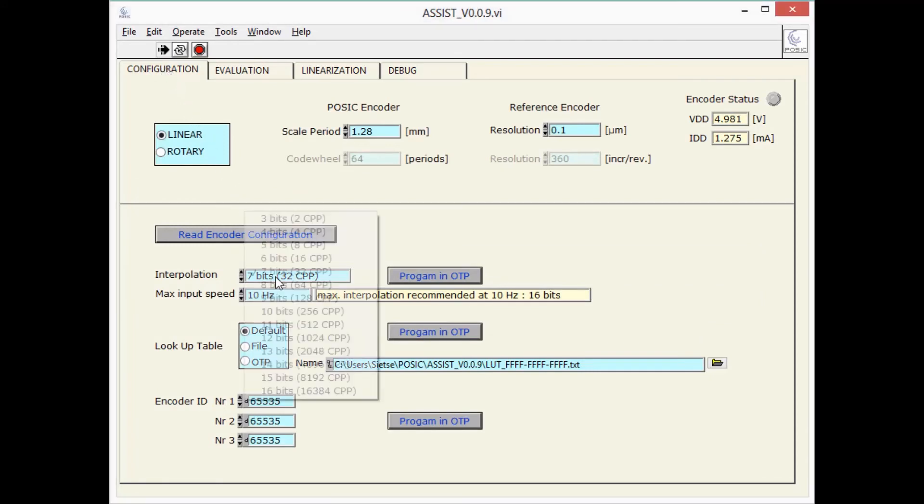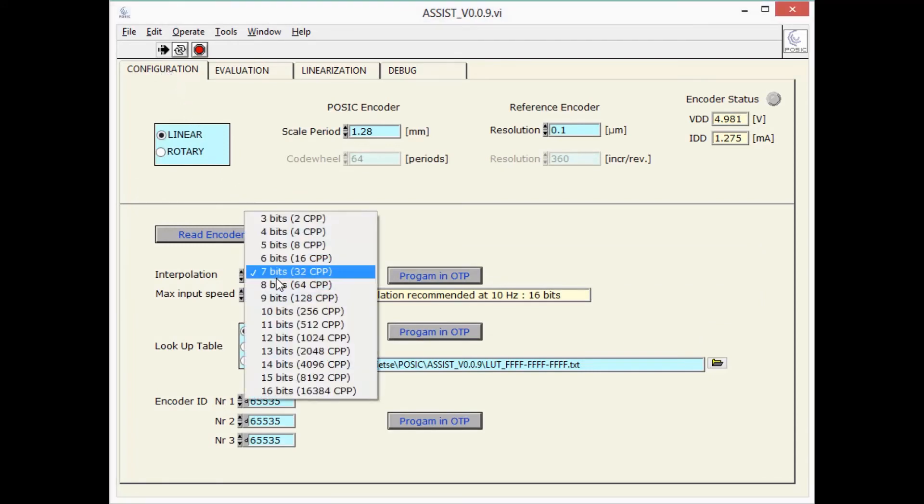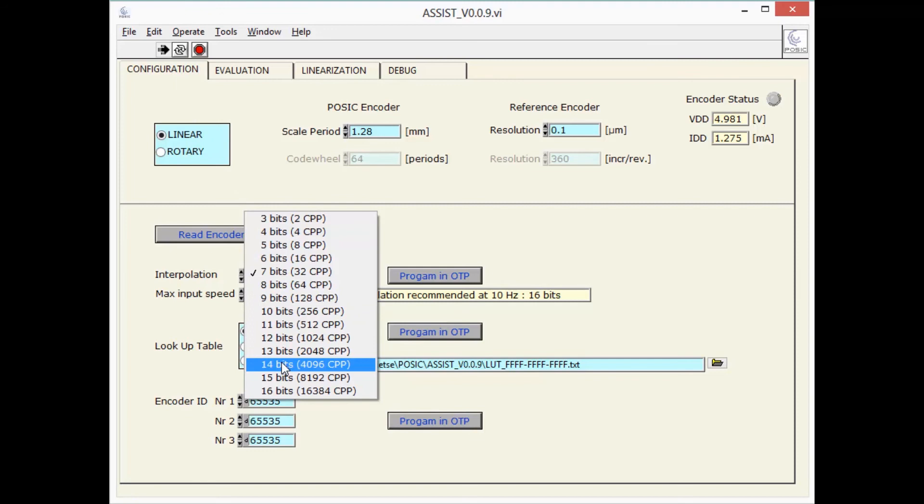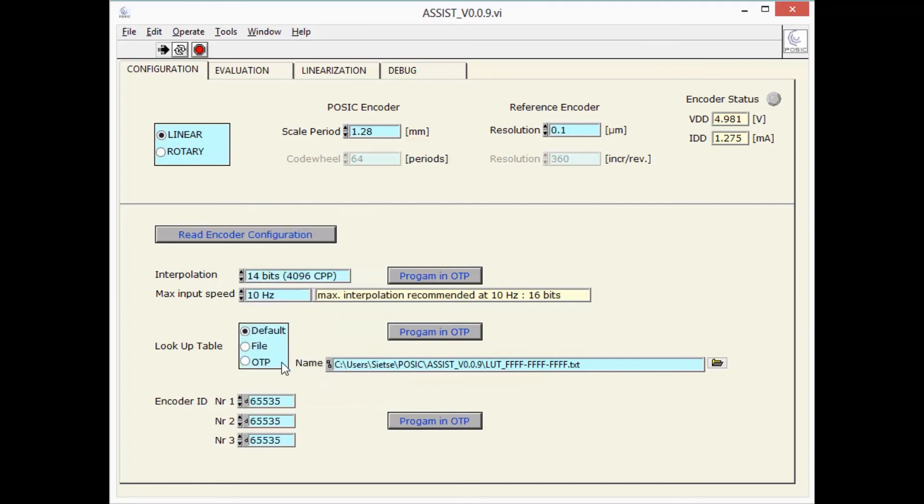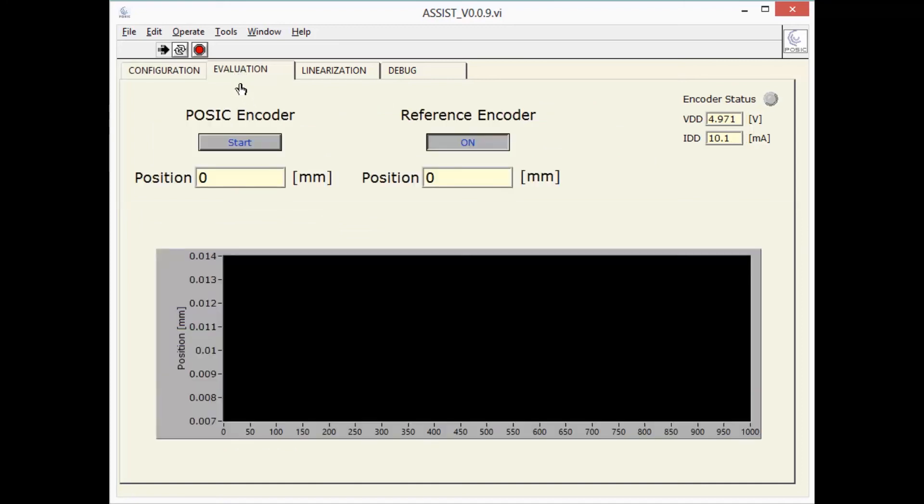I increase the interpolation from 7 bits, corresponding to a resolution of 10 µm, to an interpolation of 14 bits, corresponding to a resolution of 70 nm. The reference encoder has a resolution of 0.1 µm, or 100 nm.